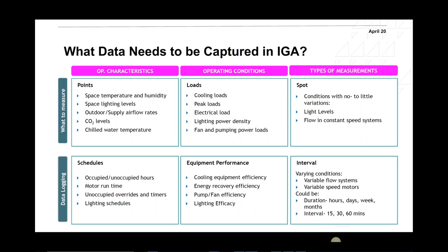Data logging: I would probably do data logging to check the schedules, when motors turn on and off, or lighting. Equipment performance: if I want to check the kilowatt per ton for a chiller, I need to put a BTU meter to check the cooling loads, and I would need to put maybe a power analyzer on the electrical side to see the kilowatt per ton. Then I compare that to the nameplate to see if there's any derating or how the equipment is being used.